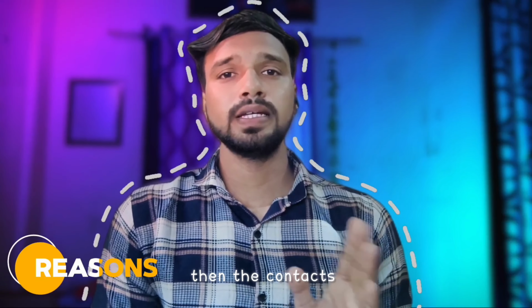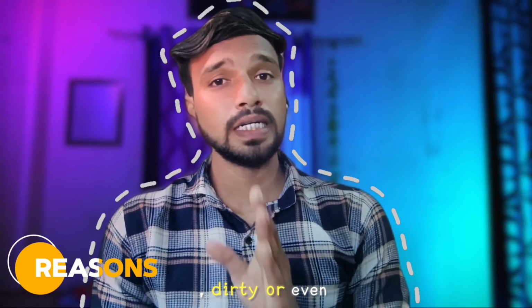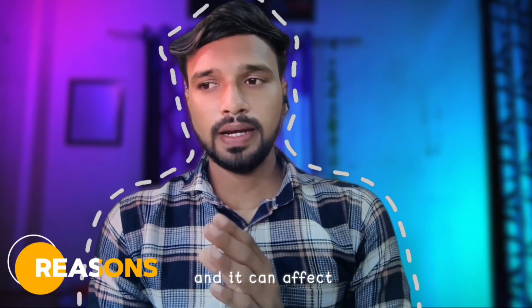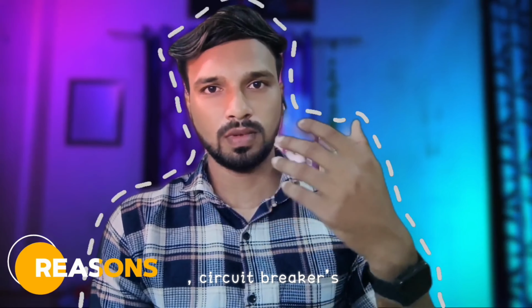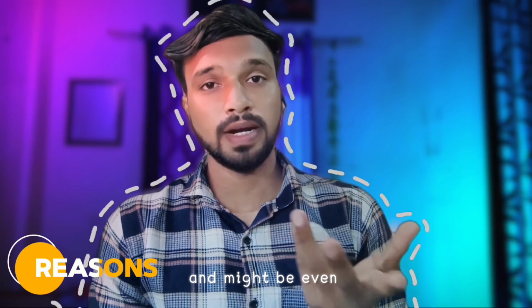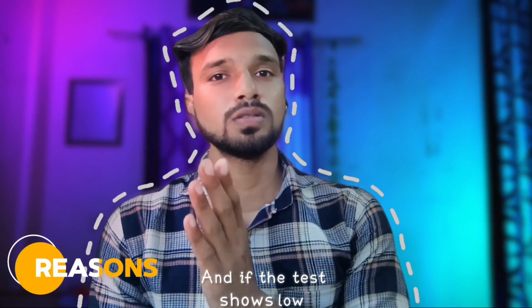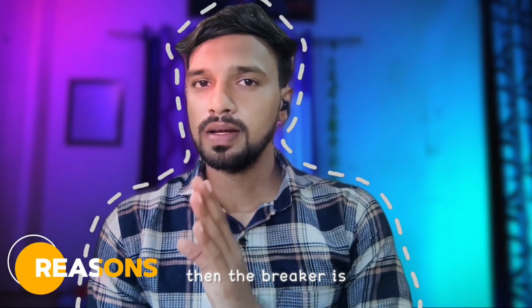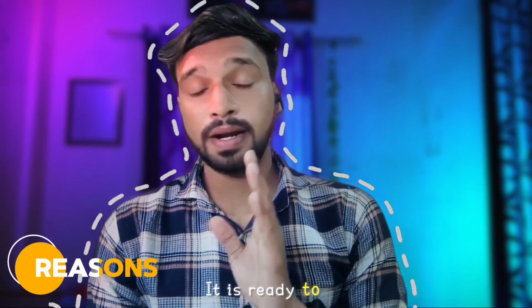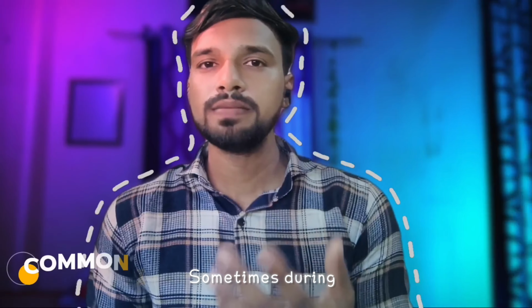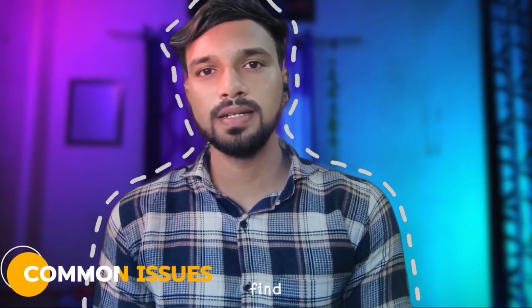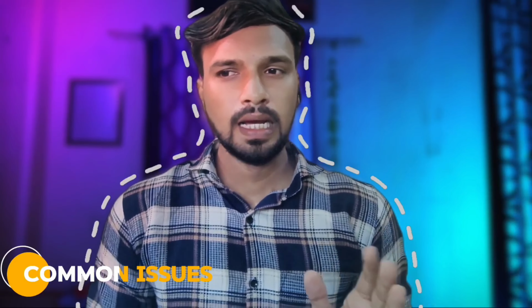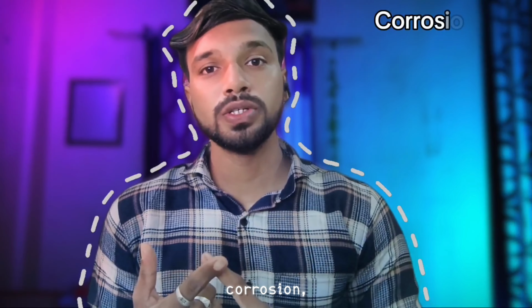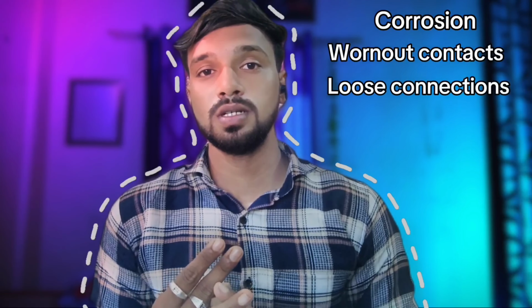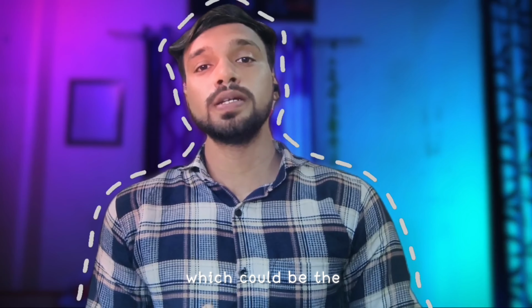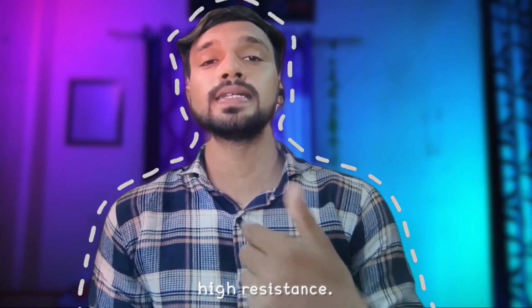If the resistance is high, then the contacts might be damaged, dirty or even worn out, and it can affect the circuit breaker's performance and might even be dangerous. And if the test shows low resistance, then the breaker is in good condition and it is ready to keep your electrical system safe. Sometimes during the test, you could find that the resistance is higher than expected. There could be some reasons like corrosion, worn out contacts or loose connections.